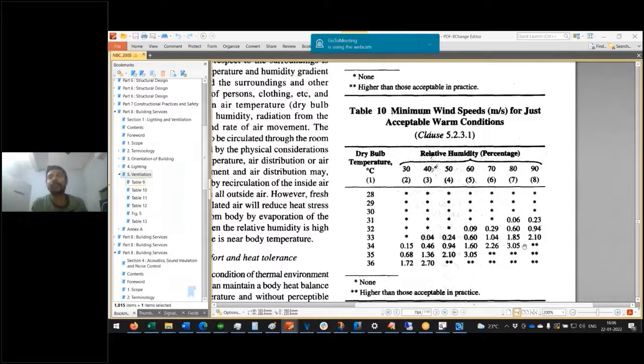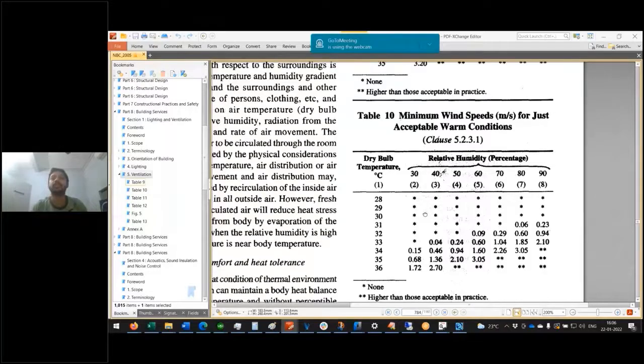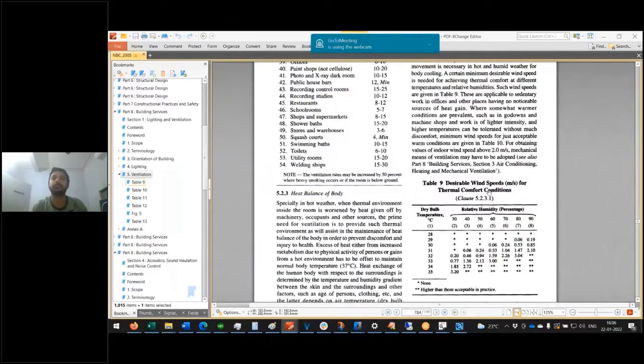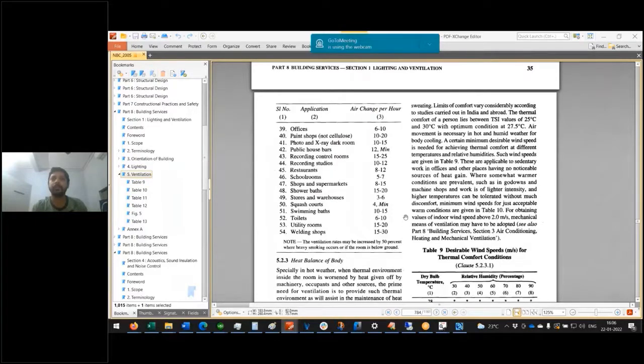So this is the speed, and then the volume of air that you want to change. You can do this calculation. The formula is velocity into area gives you the volume, right? So just use the formula Q equal to V into A, and then how many fans you have, air changes per hour. So that's the volume of air that you want to change. Okay, air changes per hour. So from that you can actually calculate.